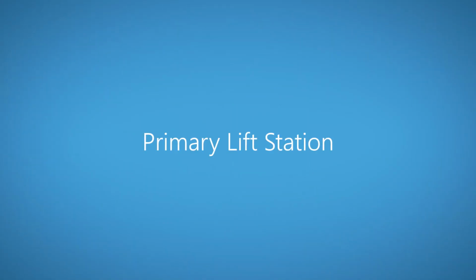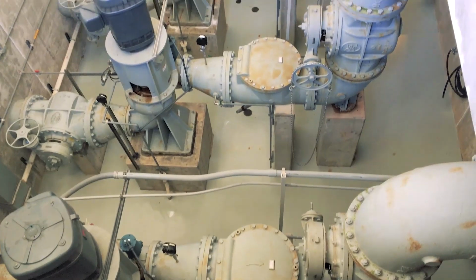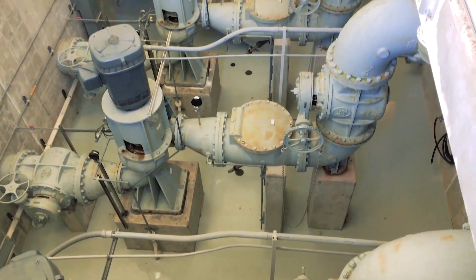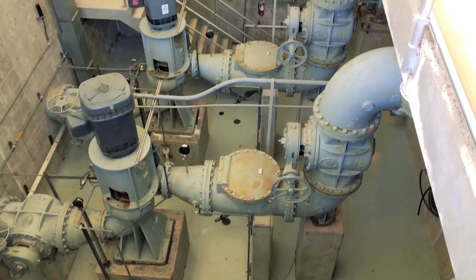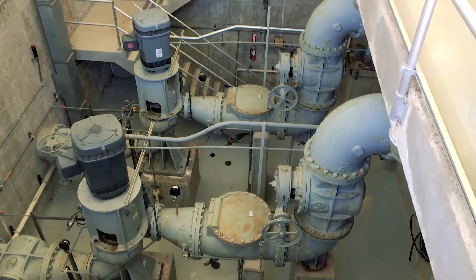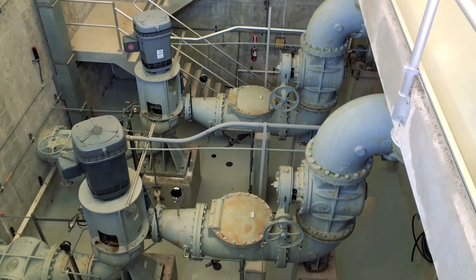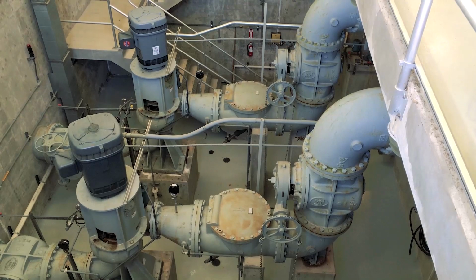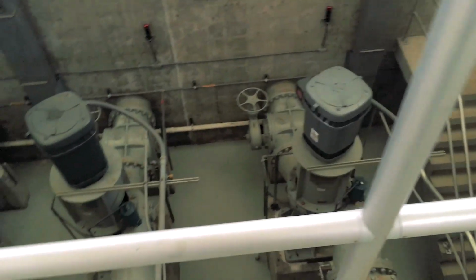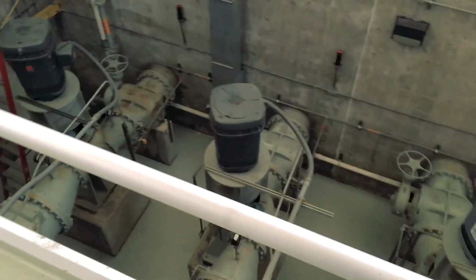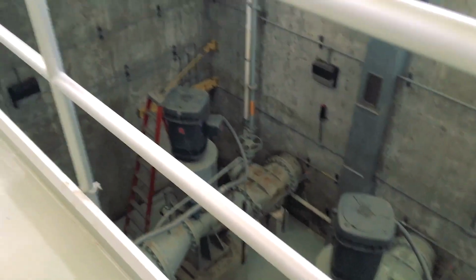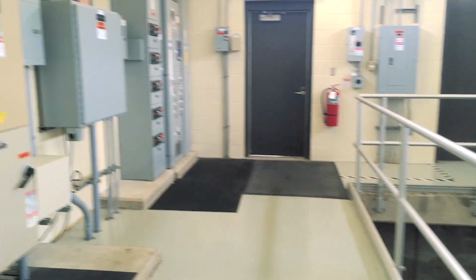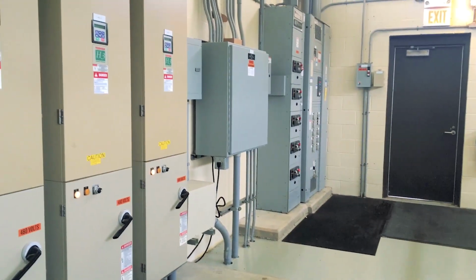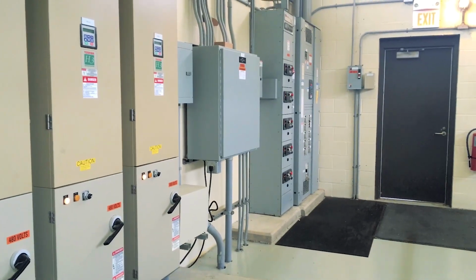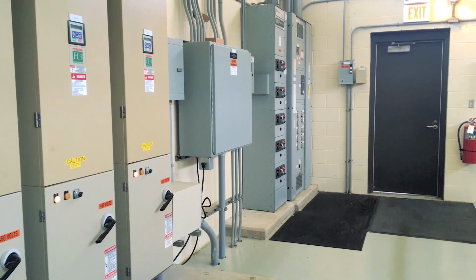The wastewater is piped from the preliminary treatment facility to the influent pump station, where 3 125 horsepower pumps move the water uphill to the primary distribution box and then onto the primary clarifiers. The influent pump station has a dry well, wet well configuration. The concrete wet well collects the sewage flow from the preliminary treatment building, while the pumps, valves, gauges, and discharge pipings are located in a concrete dry well adjacent to the wet well.